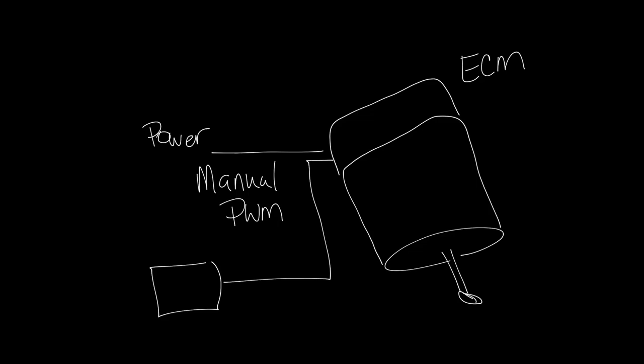Most manufacturers offer a choice of speed controls for ECMs. There's usually a manual model and a so-called remote model available. The manual PWM speed control typically provides an adjustment knob or potentiometer to set the motor speed. This usually includes a digital display or LEDs to provide feedback in terms of motor RPM and/or percent duty cycle. This allows the balancer to make settings based on published calibration charts. Some fine-tuning is generally required in order to achieve the plus or minus 5% repeatability expectation in our industry.